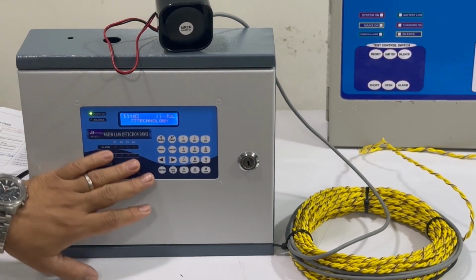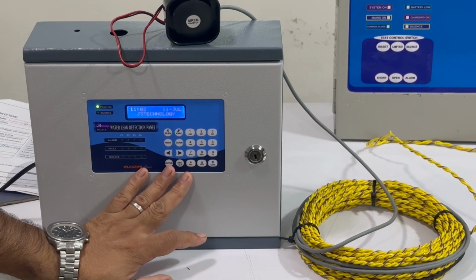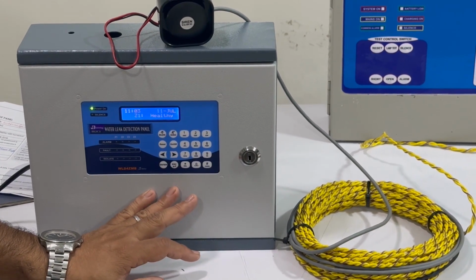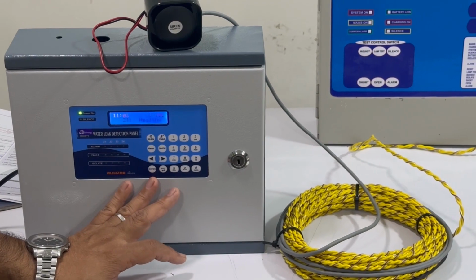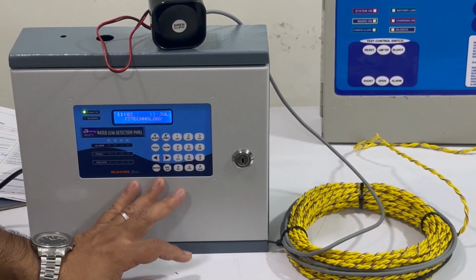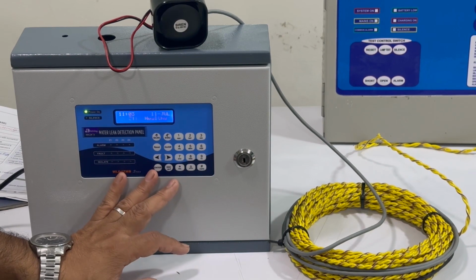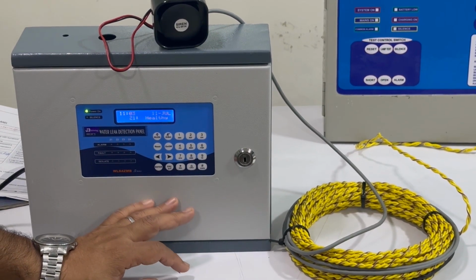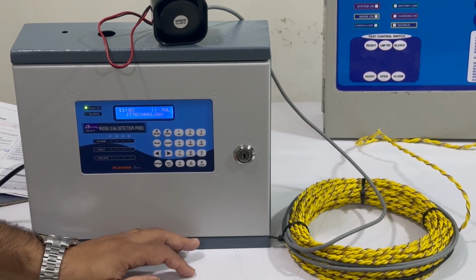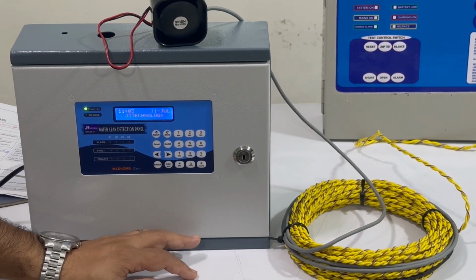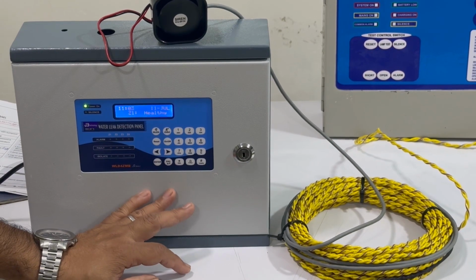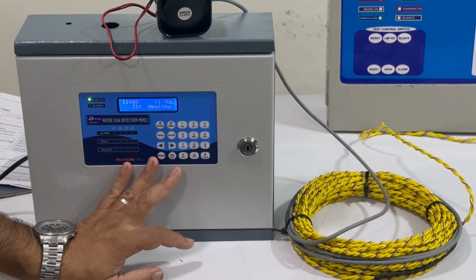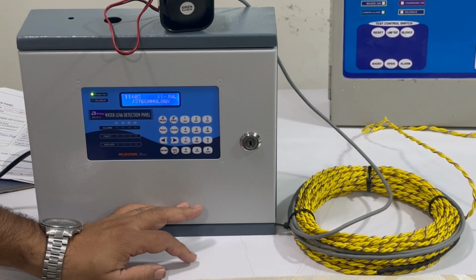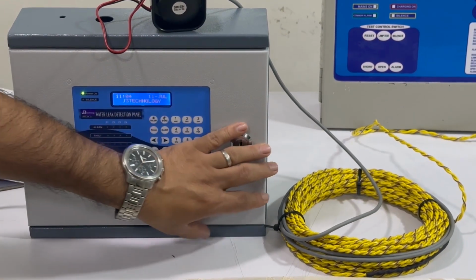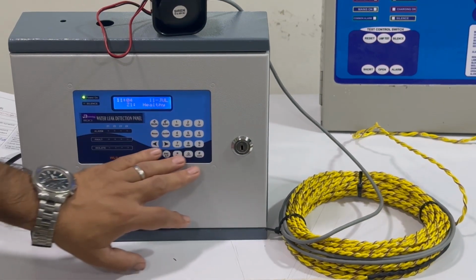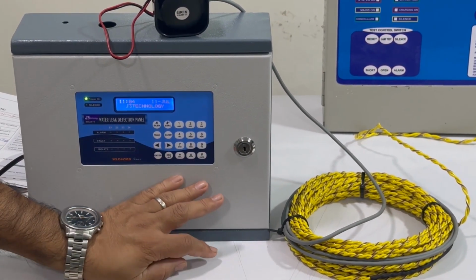The communication port for Modbus in this panel is an RS485 port, which works on 9600 or 19200 baud selectable, 8 data bits, 1 stop bit. There is also an RS232 port for firmware download. It works as a 485 Modbus RTU slave. Terminal emulation is VT100 compatible. It can monitor up to 200 meters of sensor cable in a single zone, and it is based on innovative microcontroller technology.